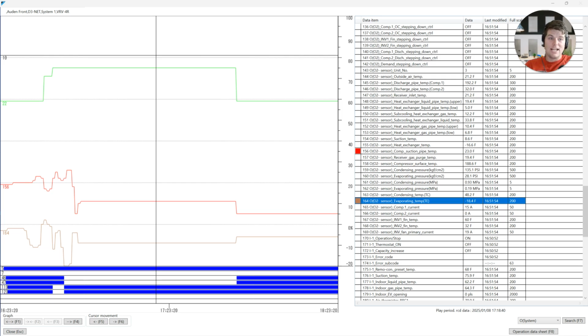High suction superheat is an indication of a lack of vapor, a lack of quality of vapor, and a lack of volume, right? This is vapor. There's no liquid. There's no liquid in sight. This is a desert. This line is a desert. And there is nothing coming down this pipe. 41 degree suction superheat, 143 degree discharge superheat. There is zero vapor in this line. This line might as well be in a vacuum. That's how much refrigerant's getting back to this compressor. None. This is a charge issue.